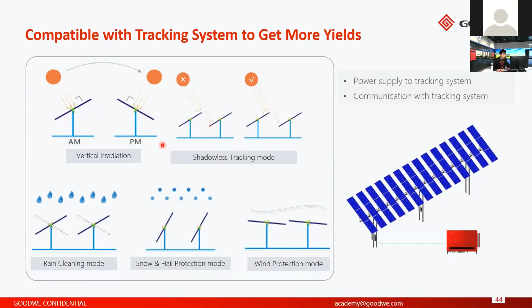And here is another specific function only for the HT series. For the HT series, not only the DC power supply, we also support the AC power supply. That means you just need to connect the AC power to the inverter, and the inverter can be started up. So in the evening, you can also do the power meter setting, and you can do the commissioning for the inverters, because you can use the AC power to power up the inverter. And also you can get 24 hours monitoring.